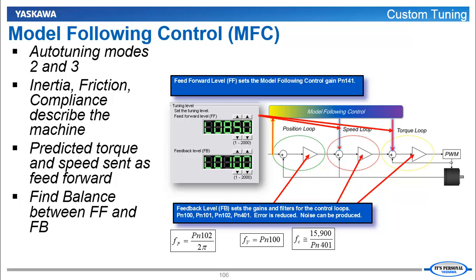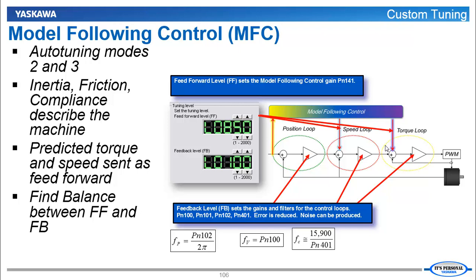Model Following Control can take the inertia from the parameter that we've set, the friction which can be detected, and the compliance of the mechanism that we've selected to build a simplified model that describes the machine. Model Following Control then takes the position command coming into the position loop—this is the command in our case right now from Program Jog or from the controller when the controller is connected. And based on that position command, predicts the speed and the torque that the motor will need based on the model. This is called a feed forward: speed feed forward and torque feed forward. And that's literally the level that you are adjusting here—is how much of this feed forward is injected into the speed and torque loop.